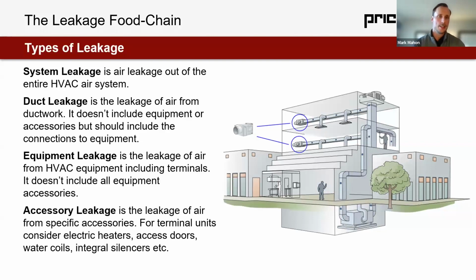Tom talked a lot about duct leakage, so the leakage of air from ductwork. The important thing I want to note is system leakage includes all of the leakages below. Duct leakage is just duct leakage. It doesn't include equipment or accessory leakage. It does include those transverse joints or wall penetrations, so potentially ductwork mating up to equipment, but it does not include equipment whatsoever. Equipment leakage, therefore, is not tested and not managed at all by standard leakage language from SMACNA or ASHRAE, and that's the leakage specifically from HVAC equipment.